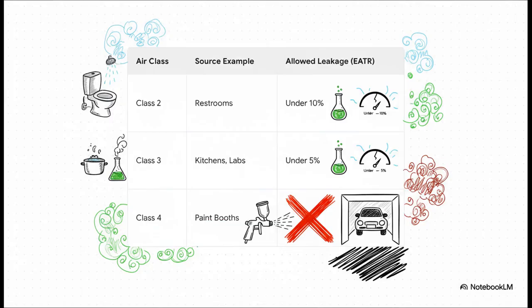Well, the answer is yes, but only if you follow the rules. And those rules are set by a standard called ASHRAE 62.1. It basically classifies air based on how dirty it is. For Class 2 air, like from a restroom, you're allowed a leakage, what engineers call the exhaust air transfer ratio, or EATR, of under 10%.